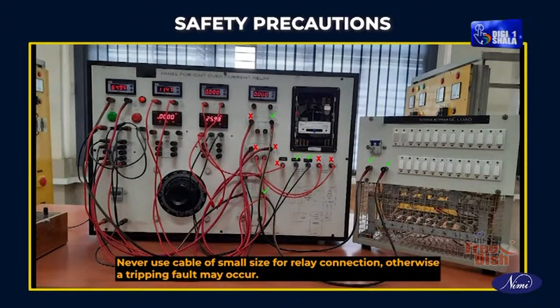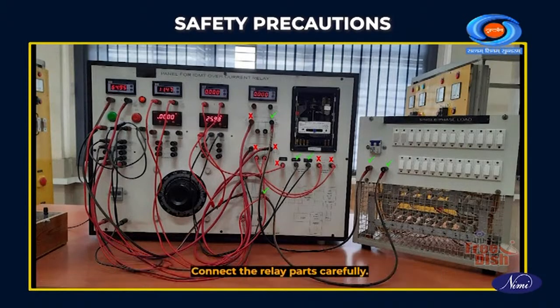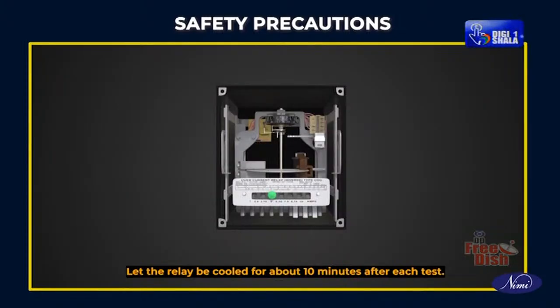Never use a cable of small size for relay connection, otherwise a tripping fault may occur. Connect the relay parts carefully. Let the relay be cooled for about 10 minutes after each test.